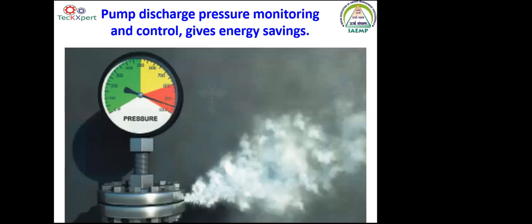The pressure gauges can be put with an impulse line, directly on a side stand, so that you monitor whether the pressure is in the green zone. Also put a marker there to show whether you are operating correctly or going out of range. Wherever it is deviating, that is a point of concern that has to be noted immediately and taken care of. Next, please.